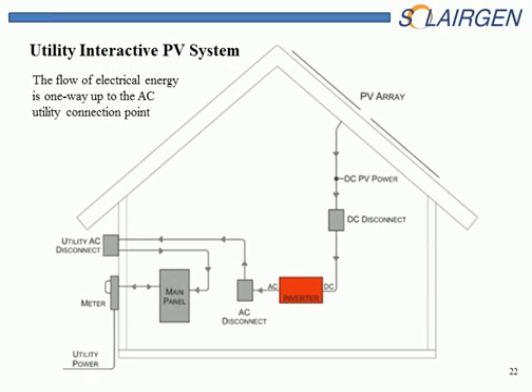This is a classic interactive inverter system setup. You have the PV array, you have the inverter, you have a disconnect from the PV array to the inverter, and you have an AC disconnect from the inverter to the main panel. In this case, we're using a string inverter for the example, so the inverter is located either inside the house or on the outside of the house. If this system had microinverters, the microinverters would be located up underneath the PV array, and they act as the DC disconnect themselves. So there's not a DC disconnect with microinverters.